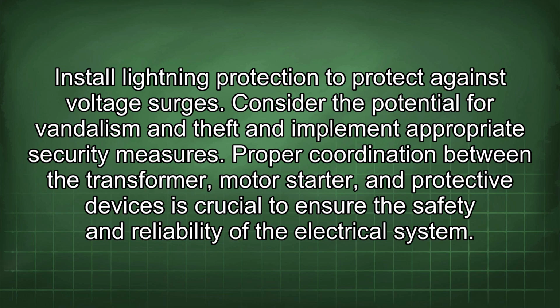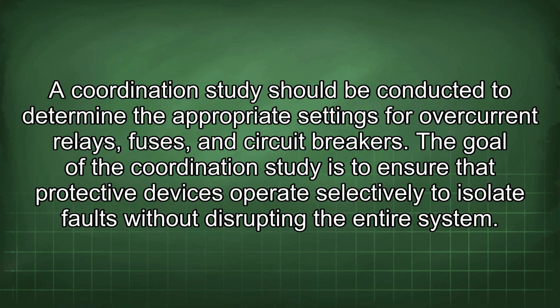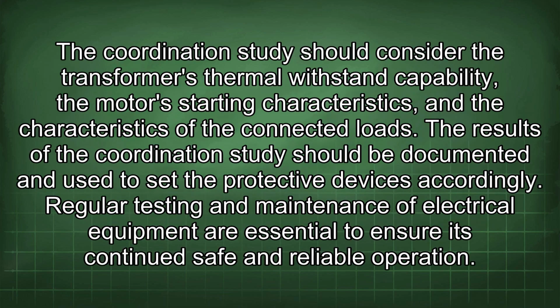Proper coordination between the transformer, motor starter, and protective devices is crucial to ensure the safety and reliability of the electrical system. A coordination study should be conducted to determine the appropriate settings for overcurrent relays, fuses, and circuit breakers. The goal of the coordination study is to ensure that protective devices operate selectively to isolate faults without disrupting the entire system. The coordination study should consider the transformer's thermal withstand capability, the motor's starting characteristics, and the characteristics of the connected loads. The results of the coordination study should be documented and used to set the protective devices accordingly.